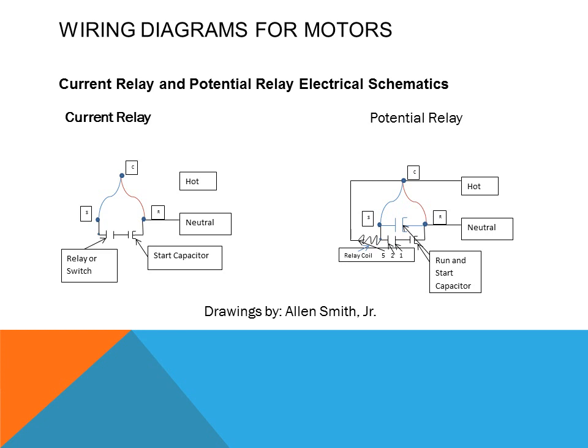There are two different wiring diagrams for these relay types. On the left is a current relay used to take out the start windings. On the right is a potential relay, which has a coil and three terminals. Terminals 5 and 2 power the coil of the start winding, and terminal 1 goes to the start capacitor. The run capacitor stays in the circuit at all times to provide additional efficiency.